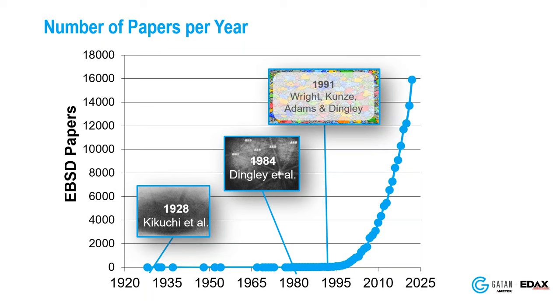Question: Is it possible to analyze organic crystals and protein crystals with EBSD? To be honest, we have not had much luck — we tend to try it every few years. The challenge is beam damage: even with a really weak, low-kV beam, we have a hard time seeing patterns before the beam destroys the sample. We do now have a direct electron detector and are using that at low kV, and we have seen some patterns, but haven't developed techniques to analyze protein patterns. We have done a few polymers — not indexing, just capturing patterns — and you can do some imaging using what we call the PRIAS technique, but nothing like what we see with metals.